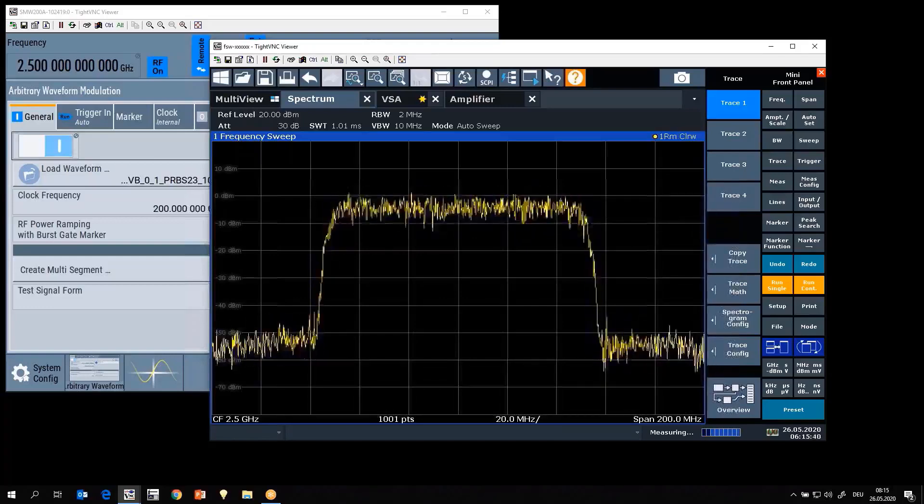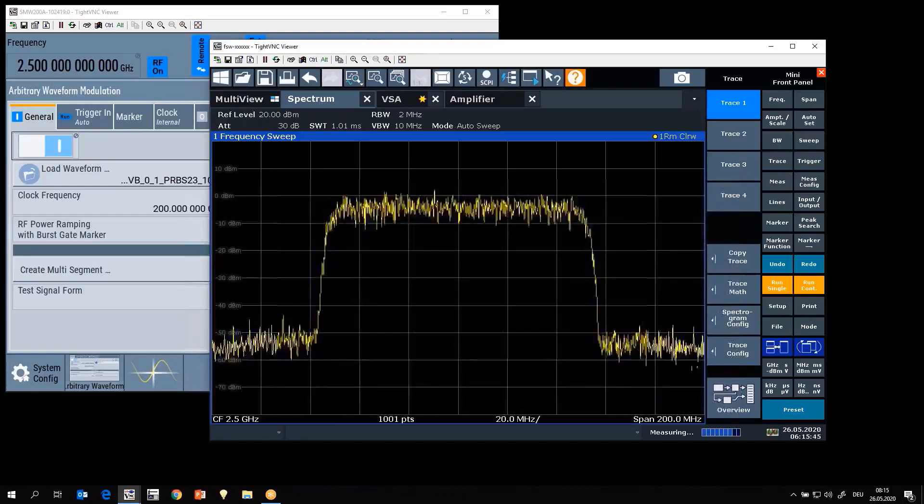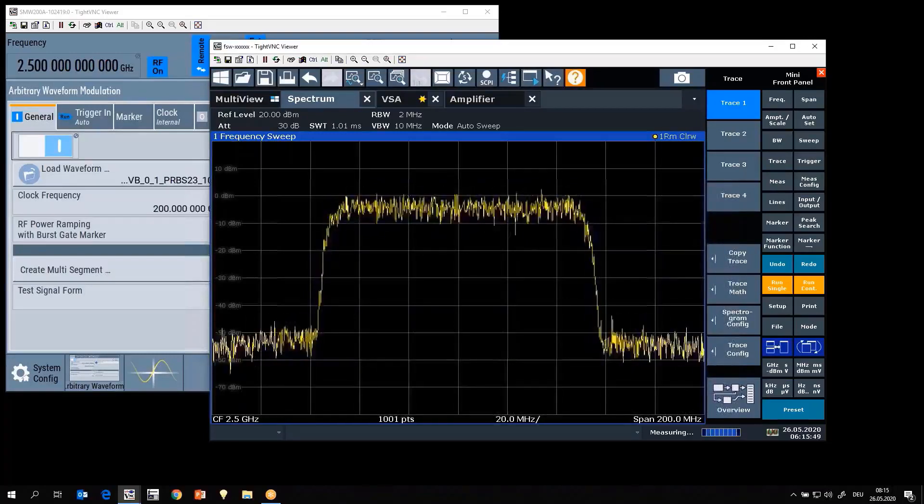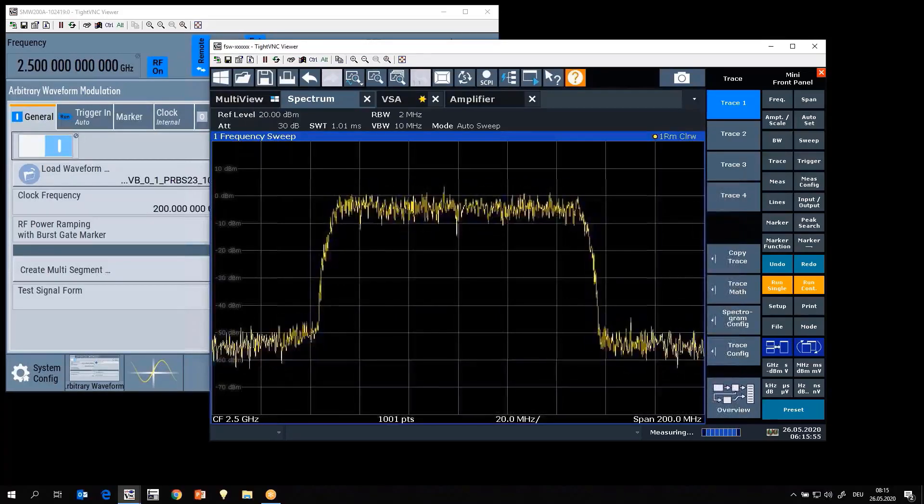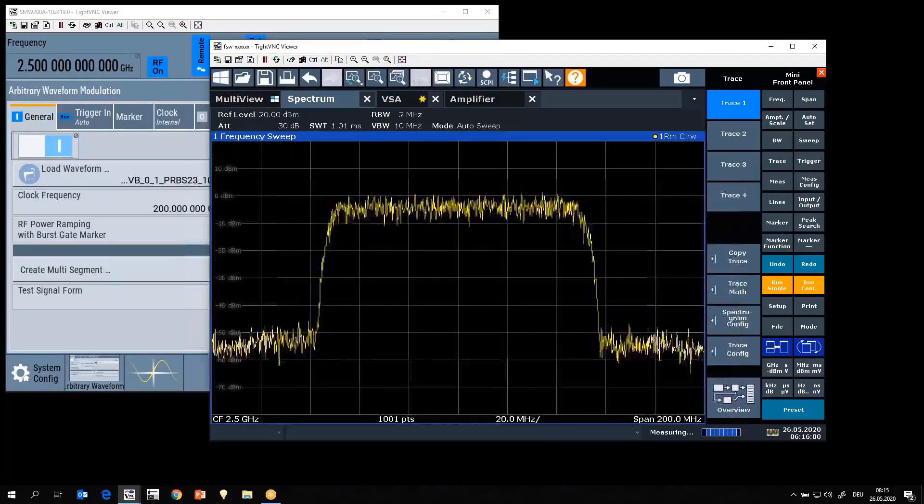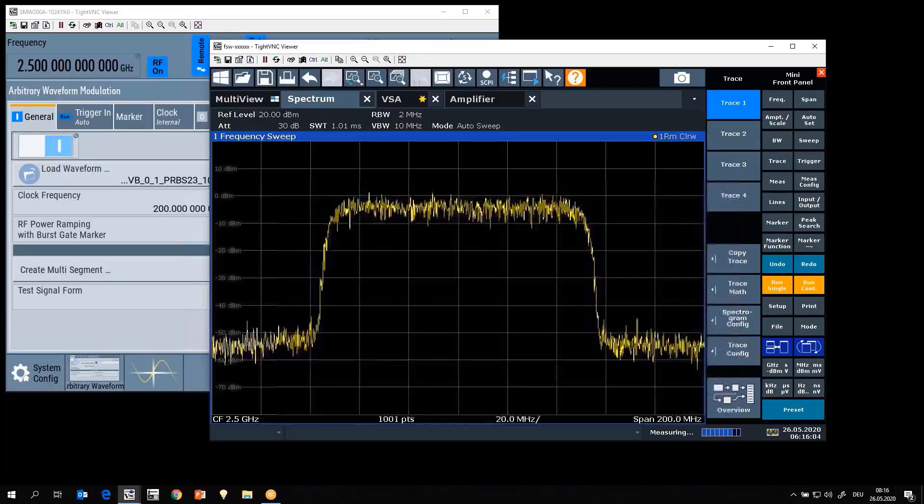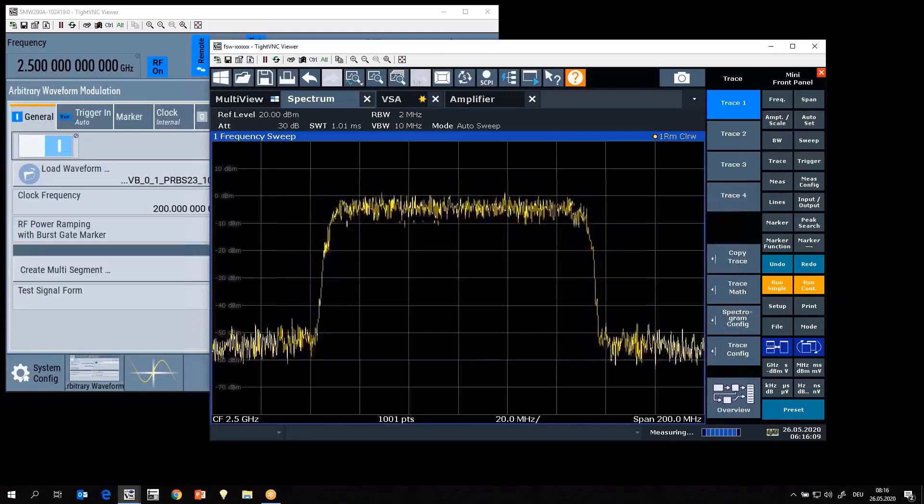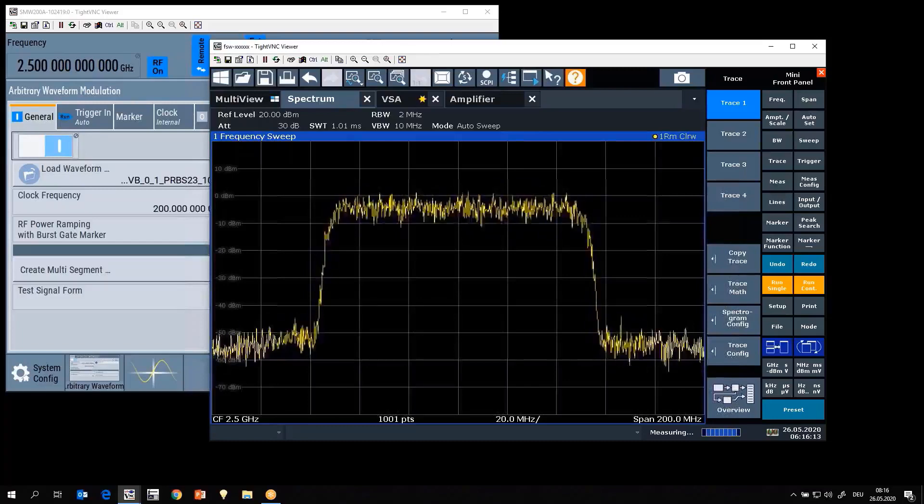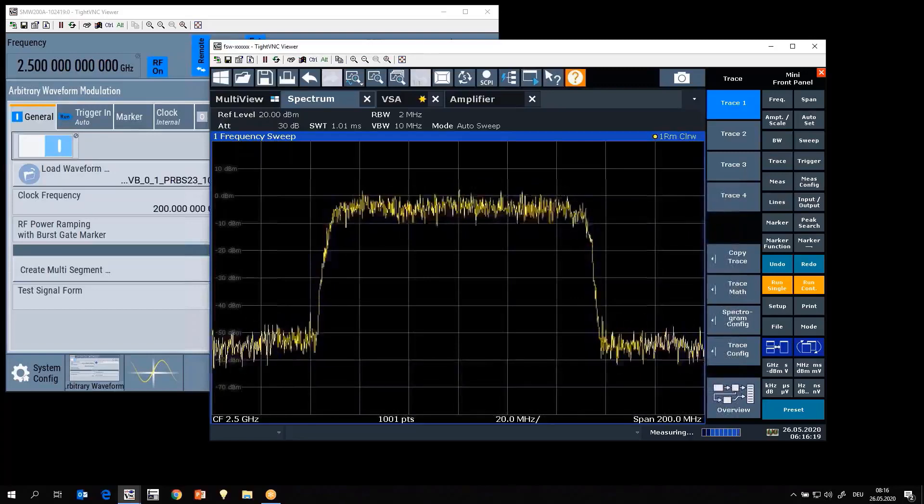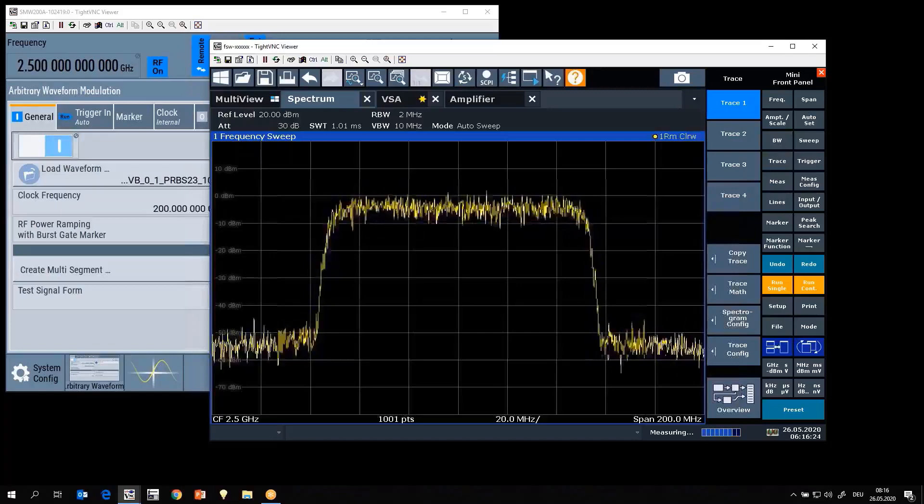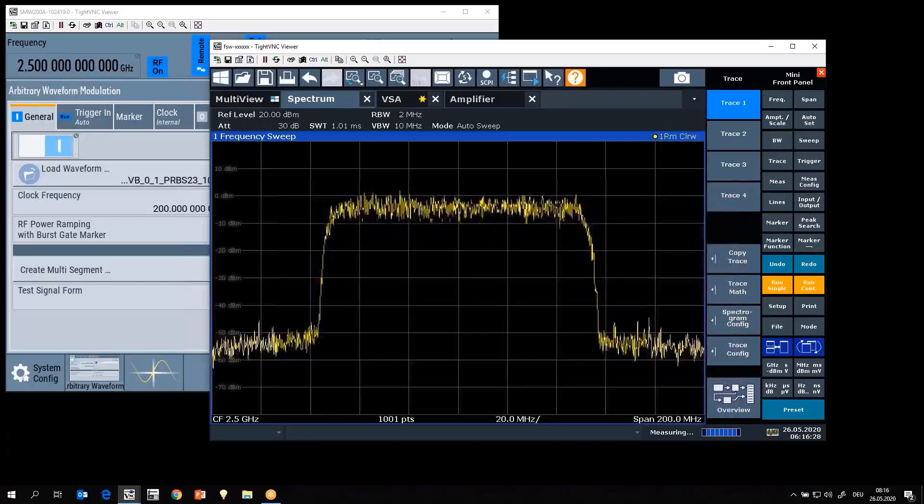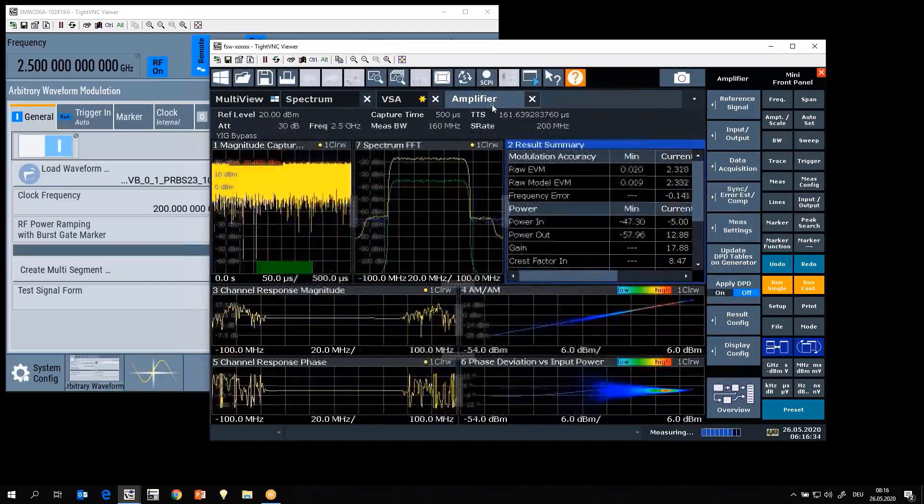Thanks Darren. Hi there again. This time we're going to talk about modulated measurements. We'll do a few different analyses on a modulated signal and we'll try to figure out what are the differences when we analyze the signal in the amplifier option, the K18, versus what we do today with single carrier signals. We'll also look at the K70, the VSA option. We finished the last video with a single carrier signal, a hundred mega symbol signal, and today I want to pick up the same signal again. So as you can see we have a modulated signal.